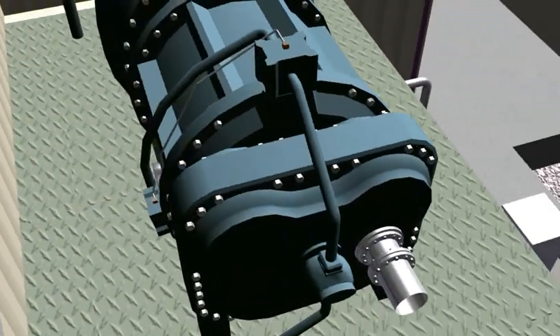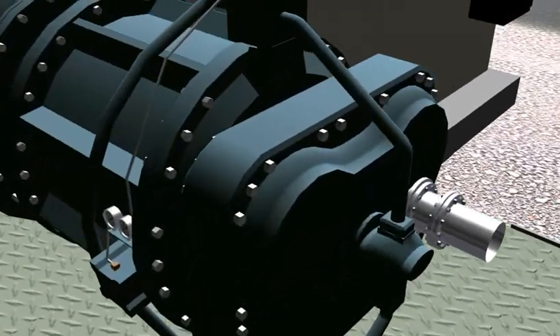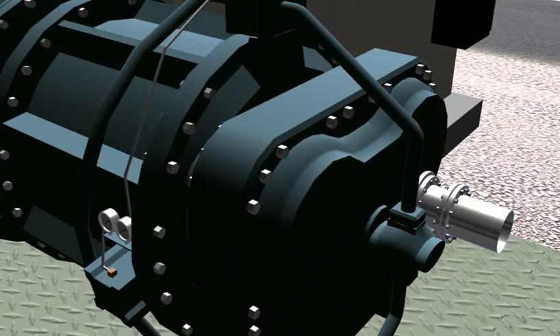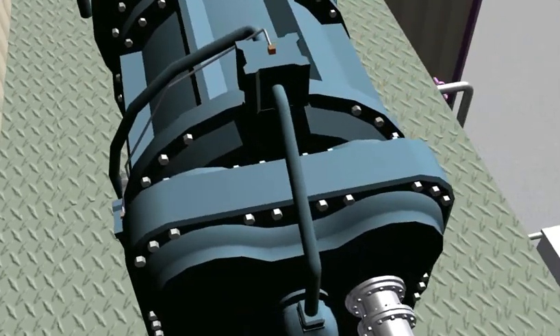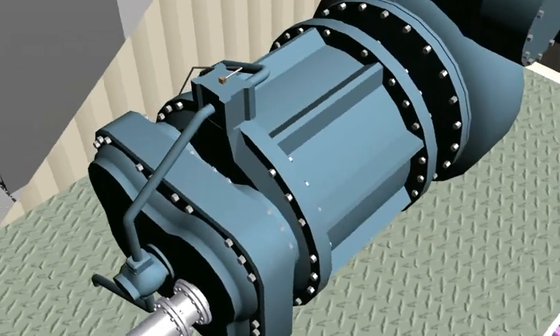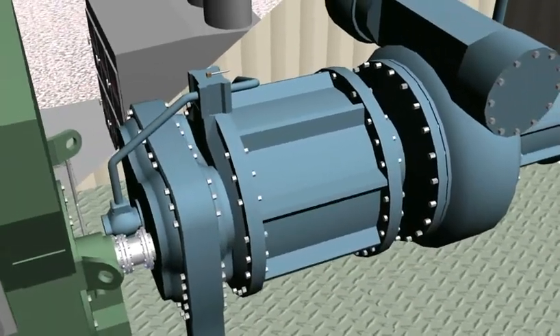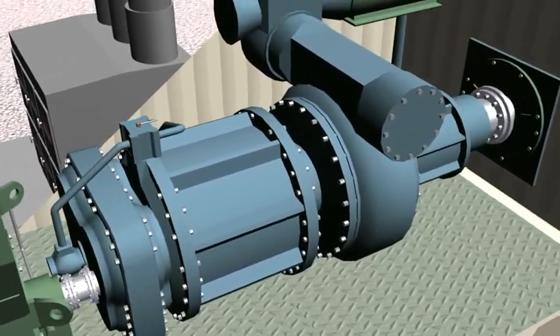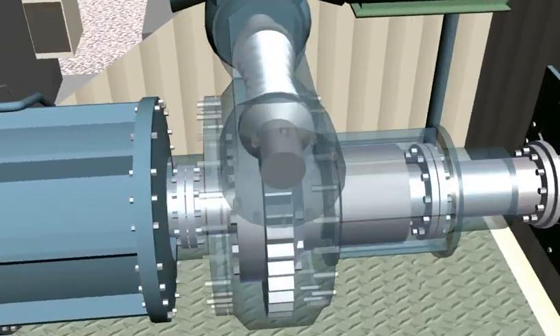Turbine lube oil supplied at approximately 15 PSIG is boosted by the torque converter charging pump to the approximately 100 PSIG required for converter operation. The charging pump is driven by the starting package 4,160 volt motor through gearing.